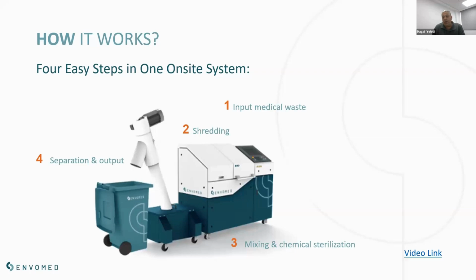Once all the waste is shredded, it goes down to a sump, and inside the sump we stream chemical sterilization with chemical disinfectant. It's peracetic acid, and it's only 1%, and then we mix it together with water. There's a 12-minute process of mixing the shredded waste with the water and the disinfectant. During these 12 minutes, we ensure that all the shredded waste is treated and totally disinfected. We reach a level of 6 log and the standard of STAATT IV.